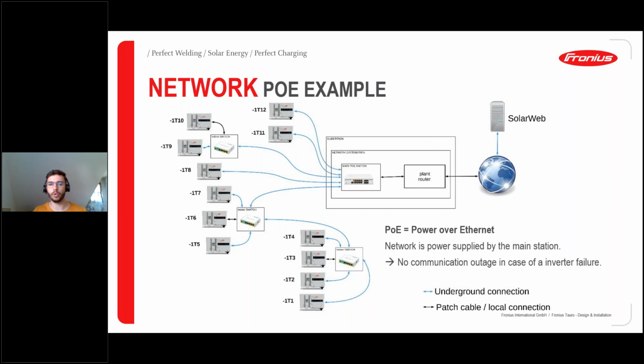This is even more critical if you have, for example, a plant controller stating how much the devices can feed in. This would be very crucial if these rules weren't followed. It's no problem with this network connection, because if one device fails it doesn't matter, all the other ones are still connected, they all have network and plant controller connections, and they follow the guides and rules of the plant controller without any problem.